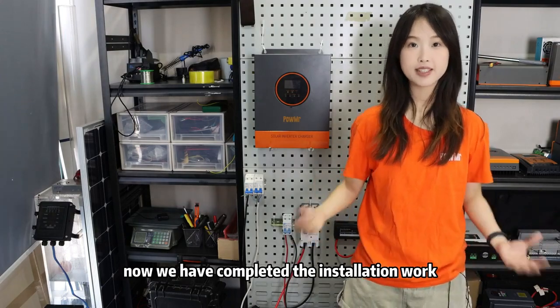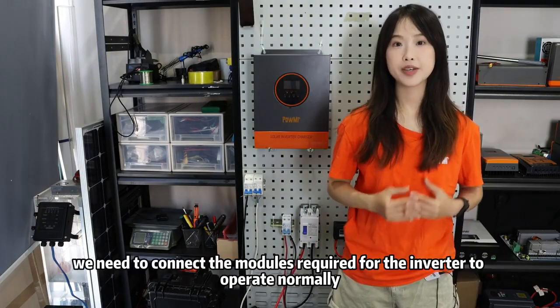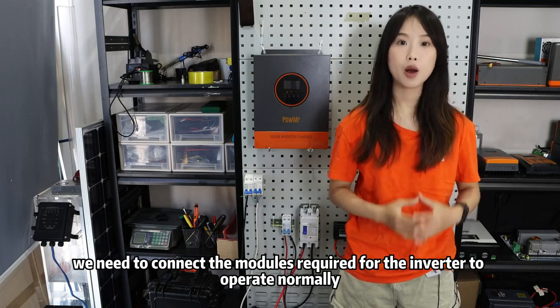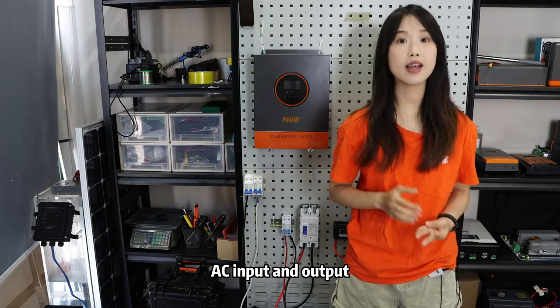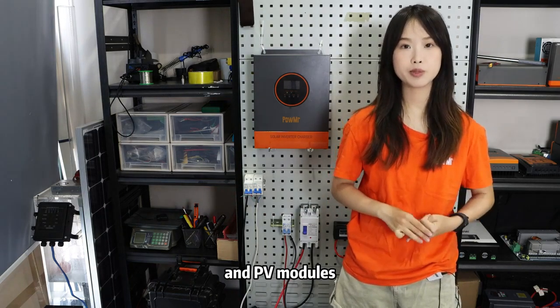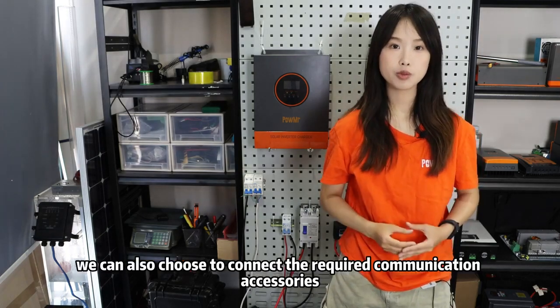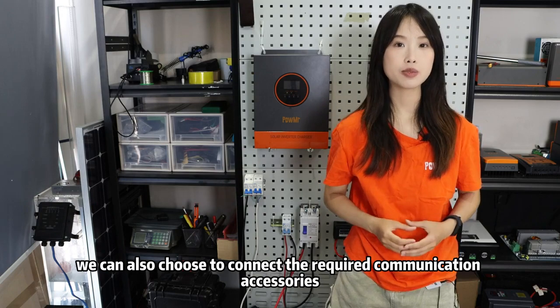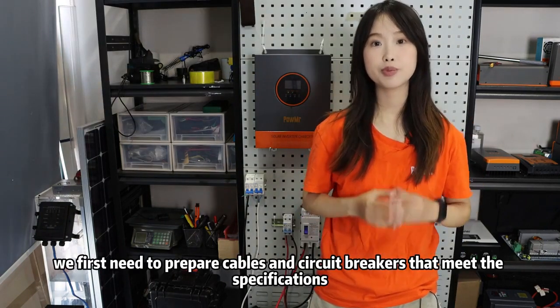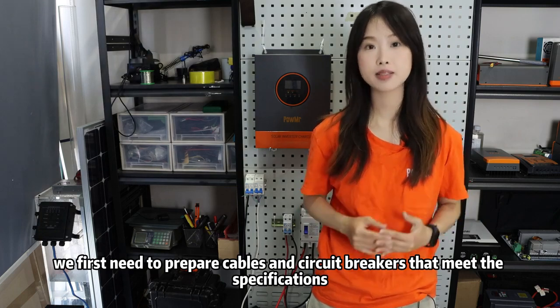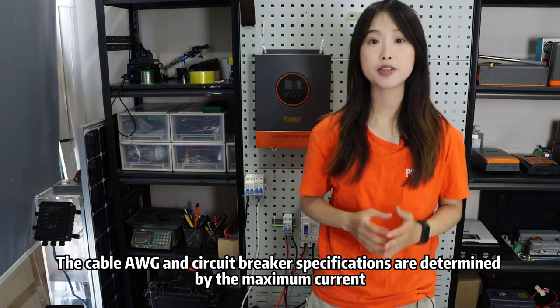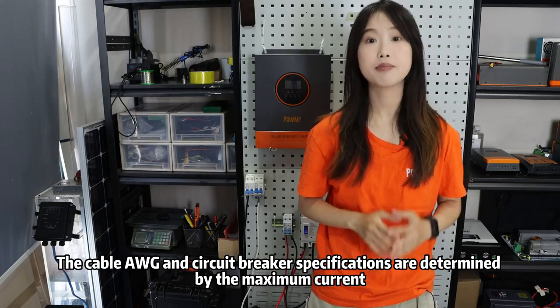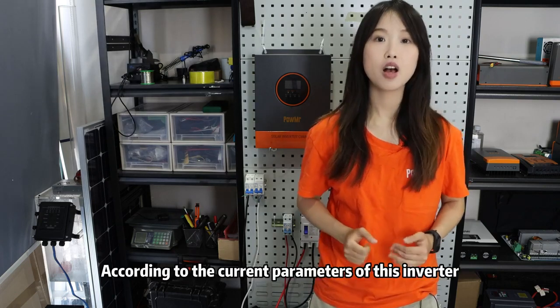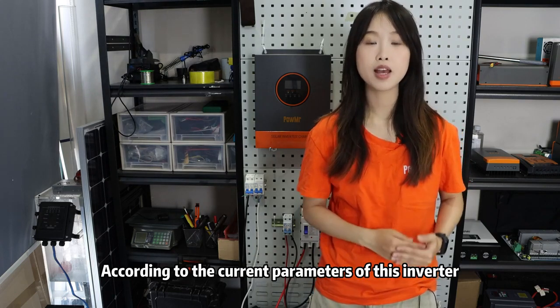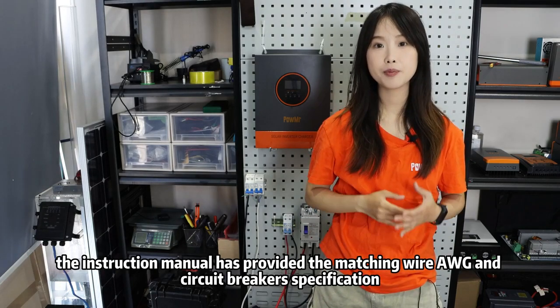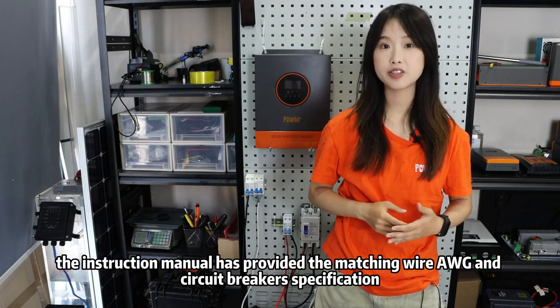Okay, now we have completed the installation work. Next, we need to connect the modules required for the inverter to operate normally, including the battery, AC input and output, and the PV modules. In addition to these main modules, we can also choose to connect the required communication accessories. Before starting the wiring, we first need to prepare cables and circuit breakers that meet the specifications. The cable gauge and circuit breaker specification are determined by the maximum current that the cable needs to bear. According to the current parameters of this inverter, the instruction manual has provided the matching wire gauge and circuit breaker specifications.